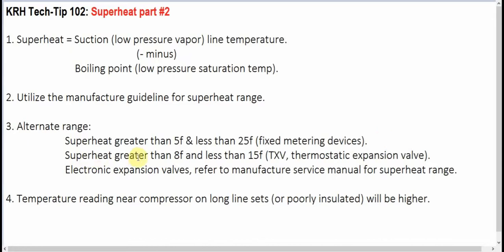The superheat usually is going to be greater than 8 degrees and less than 15 degrees with a TXV, which is a thermostatic expansion valve metering device. Now, this type of metering device regulates based on superheat. So if it is set for a 12 degree superheat, then its purpose is to regulate the refrigerant flow through the evaporator to maintain that 12 degree superheat. So the superheat setting of that expansion valve will be between 8 and 15 degrees.